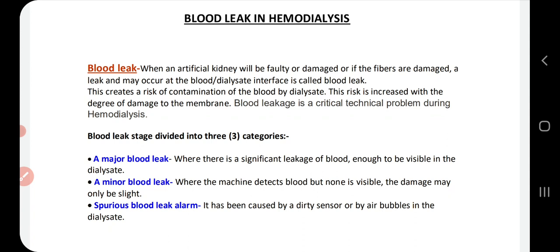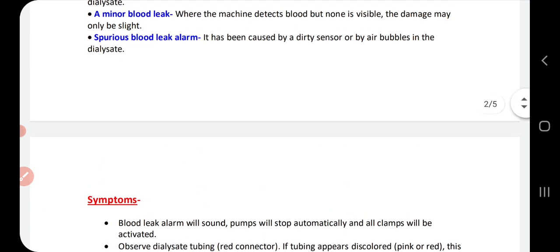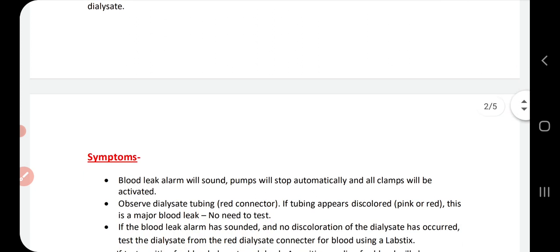We divide blood leak into three parts. First, major blood leak — you can see with your own eyes that blood has leaked out into the dialysate. Second, if you cannot see it visually but the blood leak detector alarm is triggered and a test strip is positive, that is a minor blood leak. Third, if air bubbles cause the detector to trigger and give a false alarm, that is called a spurious blood leak.